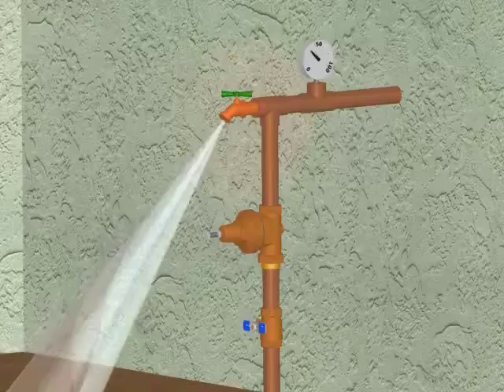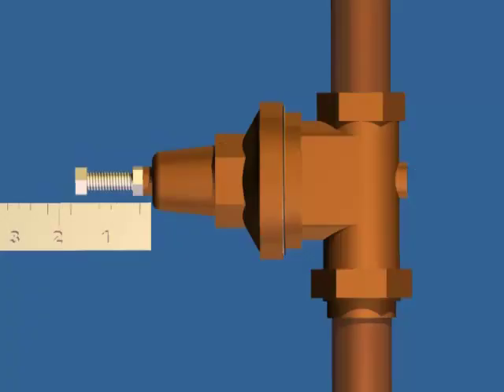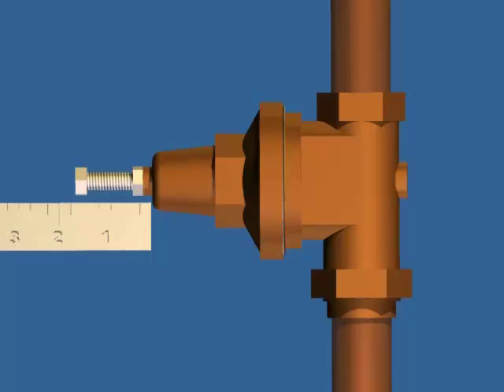You will then depressurize the valve by opening a downstream hose bib or a faucet. If you don't have a pressure gauge downstream of the regulator, you can measure the distance from the top of the adjustment bolt to the bell housing. This will allow you to readjust the valve to the proper outlet pressure after your repair.